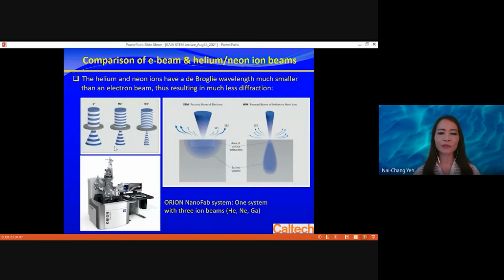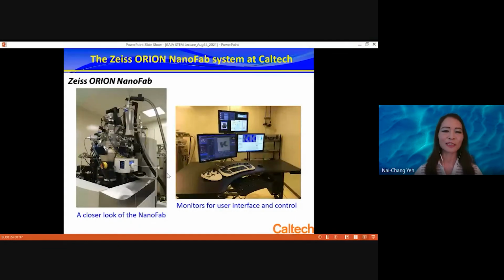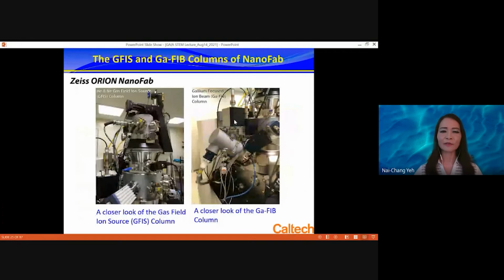This is a real example of a helium neon ion beam instrument. This system costs almost $2 million. We have one at Caltech to make structures. This is what it looks like with all the connections outside, and this is the computer screen controlling all these different processes. This system contains both a gallium beam and a helium ion focused ion beam.